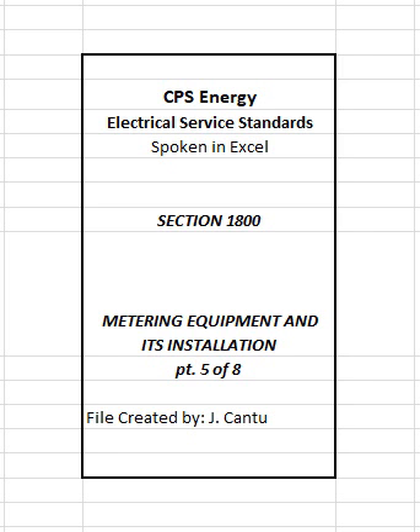Service conduits under the building or structure shall be installed as required to be considered outside of the building and shall terminate within 4 feet upon entering CPS Energy approved electric meter rooms. CPS Energy may require customer to install spare conduits and to locate meter rooms on exterior walls as close as possible to transformer poles. Refer to definition of conductors considered outside of building.